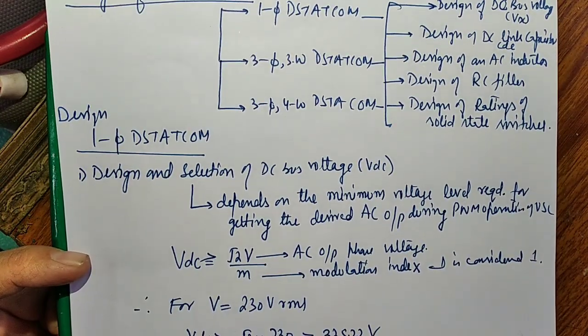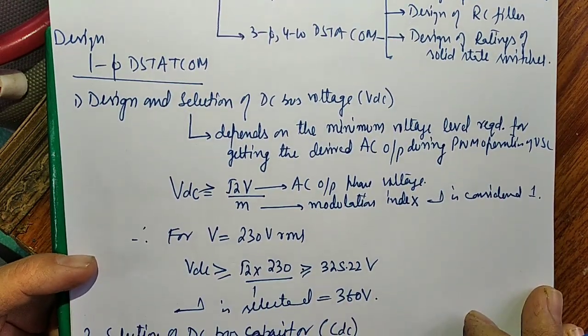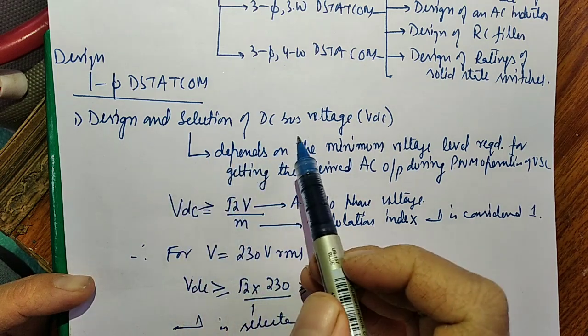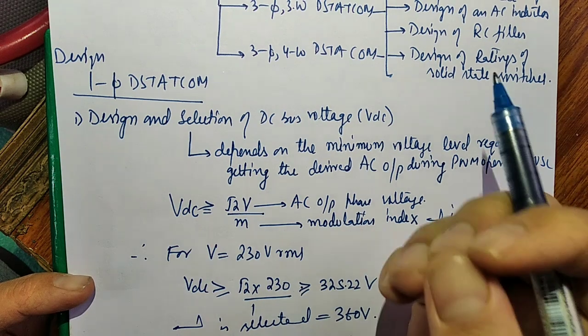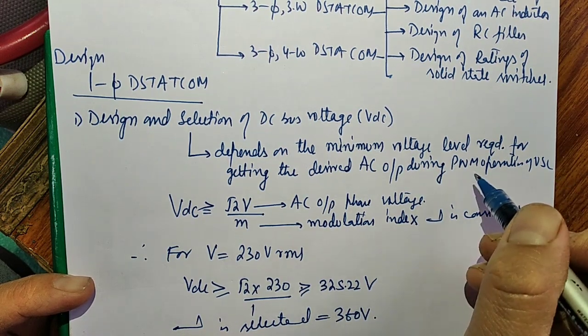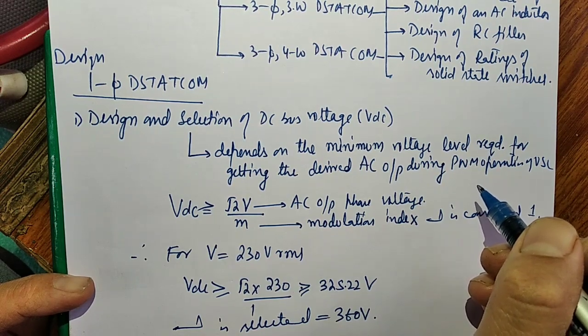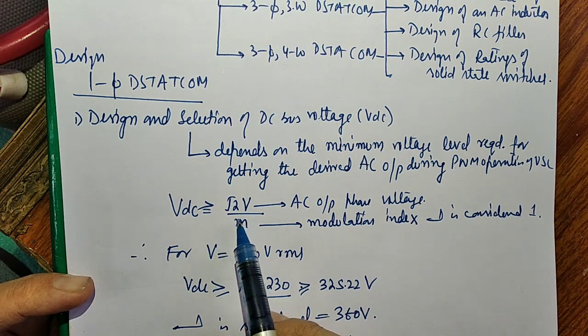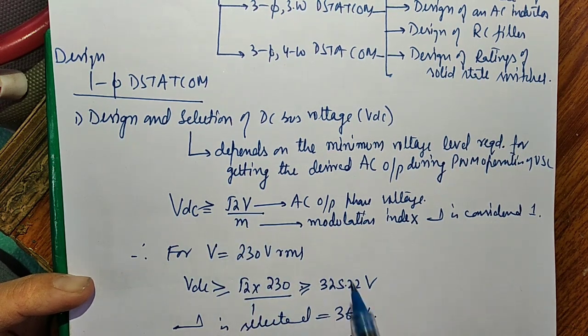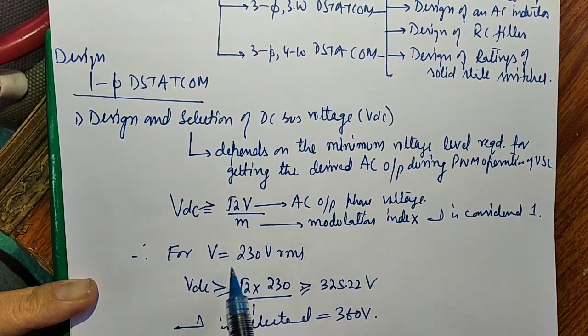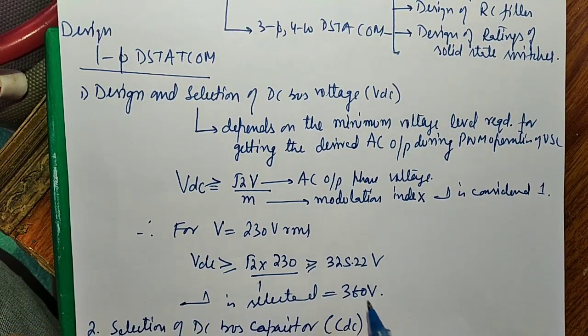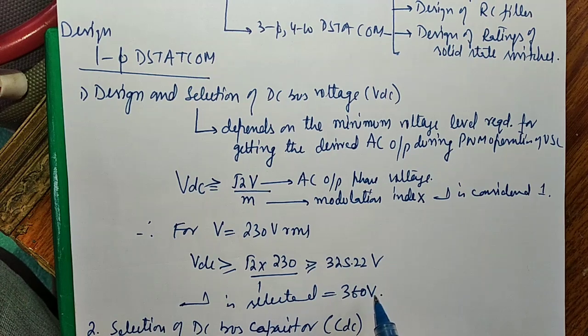We will start with the design of single-phase DSTATCOM. First, the design of the DC link bus: the selection depends upon the minimum voltage level required for getting the desired AC output voltage. VDC should be greater than the peak value of the AC phase voltage, that is V_phase multiplied by root 2. Taking modulation index M equal to 1, for V equal to 230 V, we get 325.22 V, and we set a higher margin of 360 V so that we can control it better.